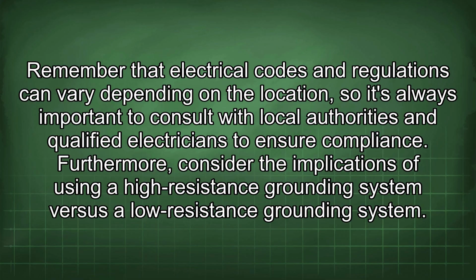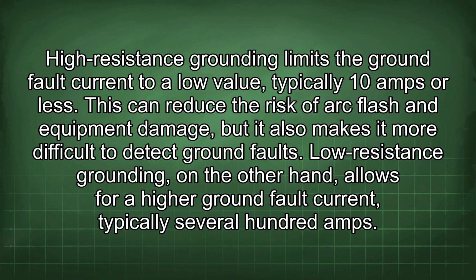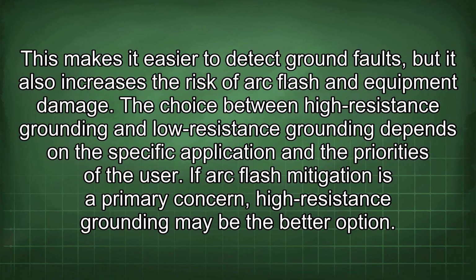Furthermore, consider the implications of using a high-resistance grounding system versus a low-resistance grounding system. High-resistance grounding limits the ground fault current to a low value, typically 10 amps or less. This can reduce the risk of arc flash and equipment damage, but it also makes it more difficult to detect ground faults. Low-resistance grounding, on the other hand, allows for a higher ground fault current, typically several hundred amps. This makes it easier to detect ground faults, but it also increases the risk of arc flash and equipment damage.